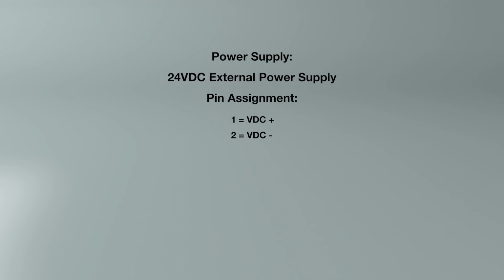Basic connections. The 9825 indicator includes a 24V DC external power supply and grounding cable for operation. The power supply and grounding cable are connected to the 9825 via the 3-position screw-down terminal connector. The ground terminal should be routed to the grounding lug on the rear of the 9825 housing and then to earth using the provided grounding cable assembly in order to optimize signal stability.